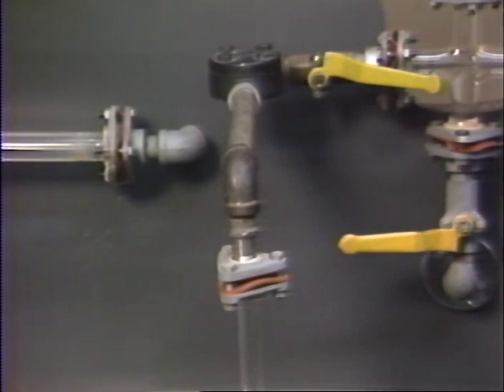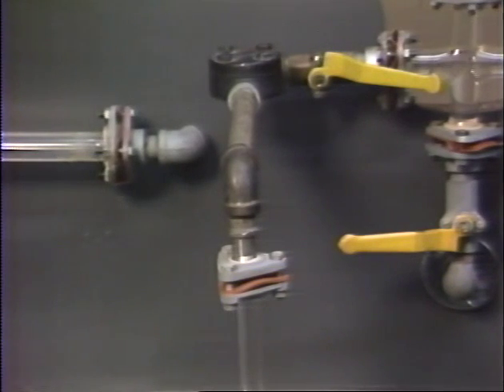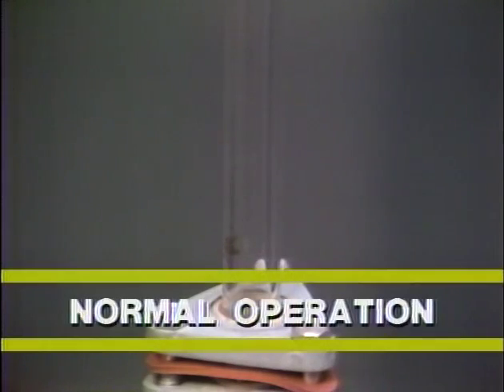The action of the disc, however, makes it one of the easier traps to test by sound. We'll use a glass discharge line so you can see the action that accompanies the sound. You should be able to hear about six cycles per minute in a properly functioning disc trap that is correctly sized.